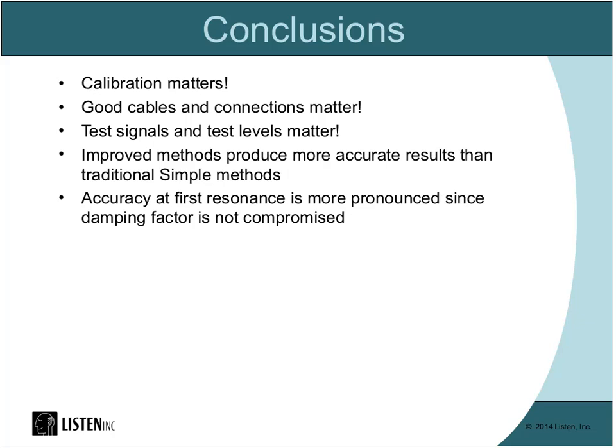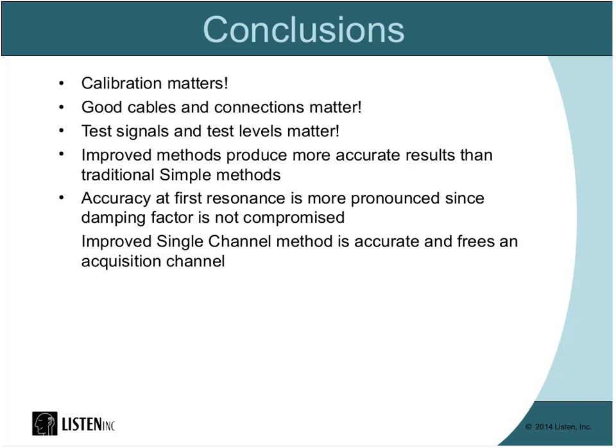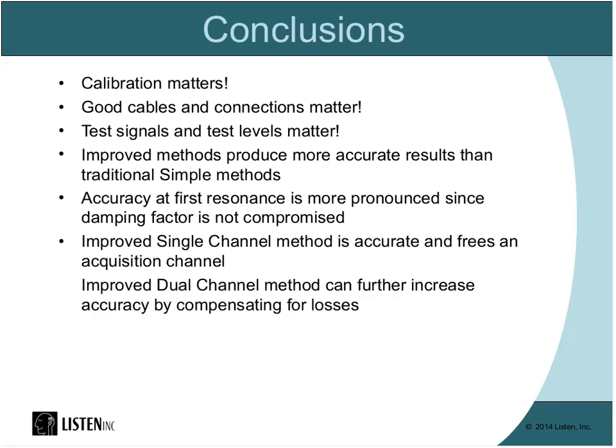So as I said earlier, the accuracy at the first resonance is more pronounced since the damping factor is not compromised. It is accurate and frees up an acquisition channel, so you could do acoustic measurement on one channel, electrical on the other.